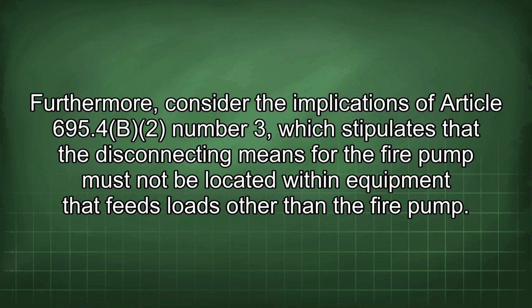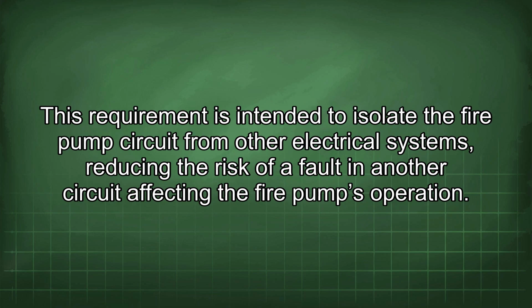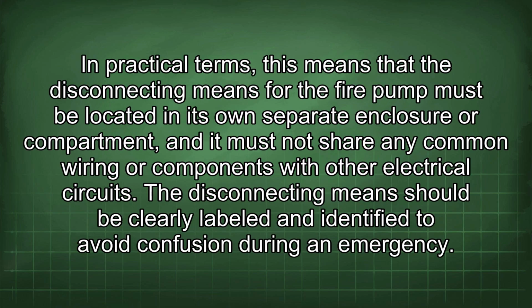695.4 B2 number 3, which stipulates that the disconnecting means for the fire pump must not be located within equipment that feeds loads other than the fire pump. This requirement is intended to isolate the fire pump circuit from other electrical systems, reducing the risk of a fault in another circuit affecting the fire pump's operation. In practical terms, this means that the disconnecting means for the fire pump must be located in its own separate enclosure or compartment, and it must not share any common wiring or components with other electrical circuits.